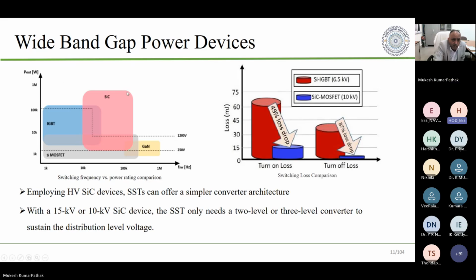Similarly, you have SiC device now. If you see this device, what it is capable of is operating at very high frequency. The limit of 10 kilohertz or 20 kilohertz is no more there in this device. It operates at hundreds of kilohertz. And it can also supply high power. You can see power is now going up to megawatt range. So this is an opportunity to use a device capable of operating at high frequency and also handling very large power. GaN devices are also there, which have further higher frequency capability, but these devices will find application in small power rating only, up to a few kilowatt, not even tens of kilowatt.